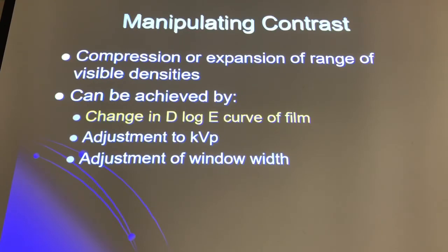So can the radiologist change it after? He can change it back too. He can do whatever he wants. Yeah, they can change it too. What is recommended is that you don't play with that. What most manufacturers will tell you is to leave it alone, because they say, and I don't know if it's true or not, that when you start manipulating it, you are cutting the ability of the radiologist to change a wider scale, that you limit the radiologist by doing that. I think it's true for some systems, and for other systems, I think they just don't want you touching it.